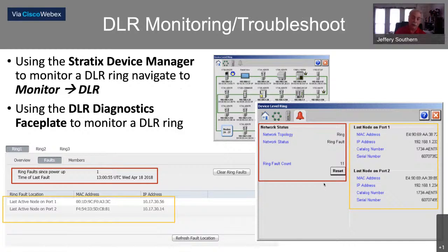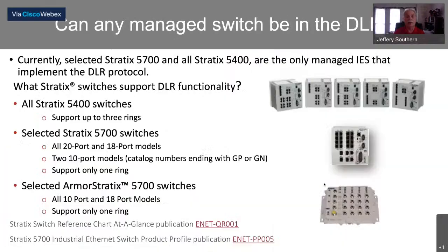So if you set up a DLR ring and it opens up into a linear bus, and the next cable somebody pulls, you're going to have a problem. It's important in a DLR ring, or any device ring, to monitor the health of that ring.